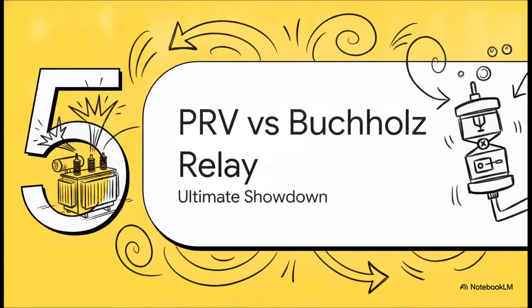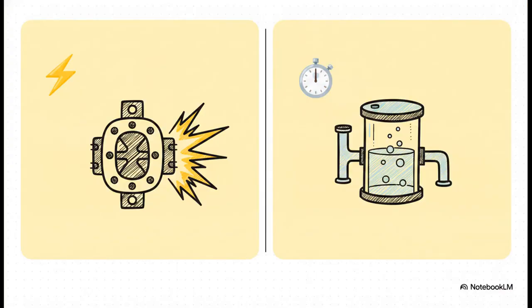All right, bringing us to part 5, PRV versus the Buchholz relay, the ultimate showdown in transformer protection. To really appreciate the PRV, we need to compare it to its famous counterpart in power systems, the Buchholz relay. On one hand, we've got ultra-fast mechanical pressure detection with the PRV. On the other, moderate-speed gas accumulation detection with the Buchholz. They're both heavily relied upon to protect the transformer, but they operate on entirely different physical principles to catch entirely different types of failures.